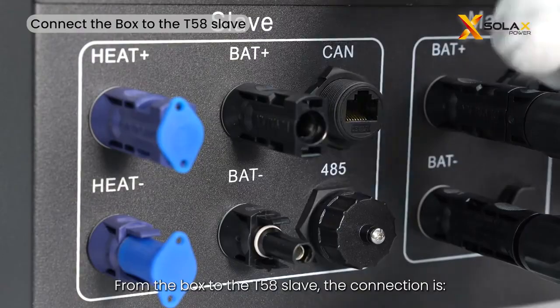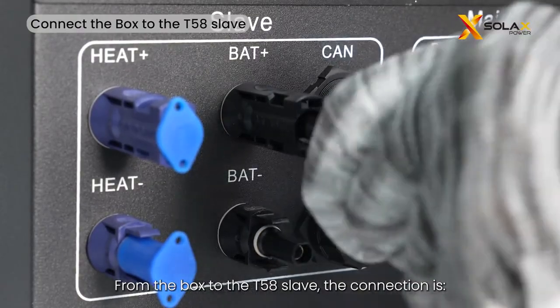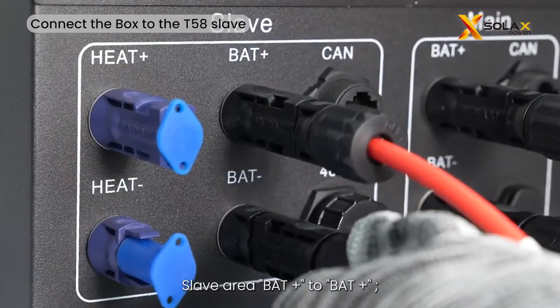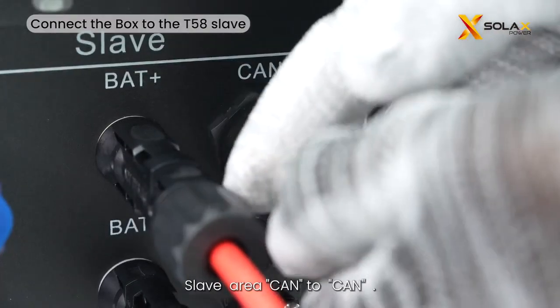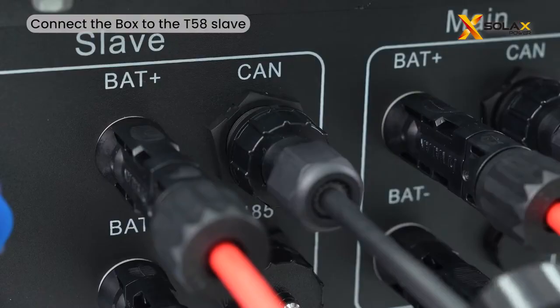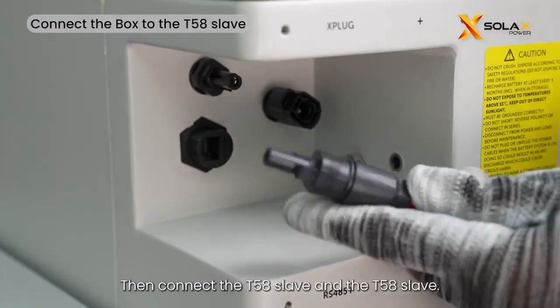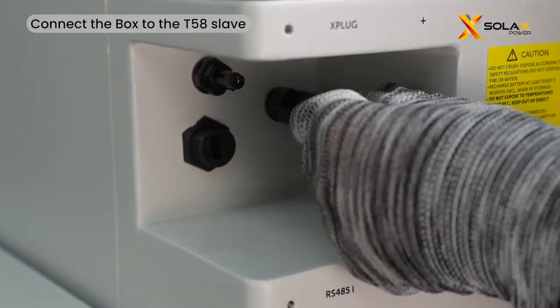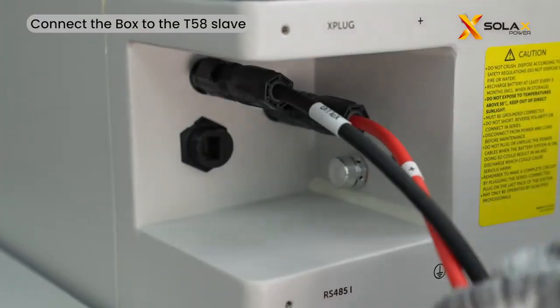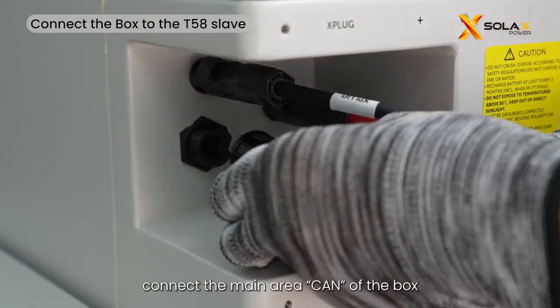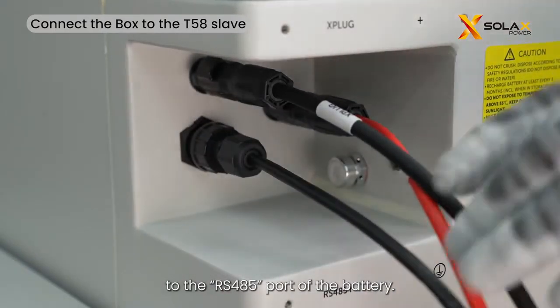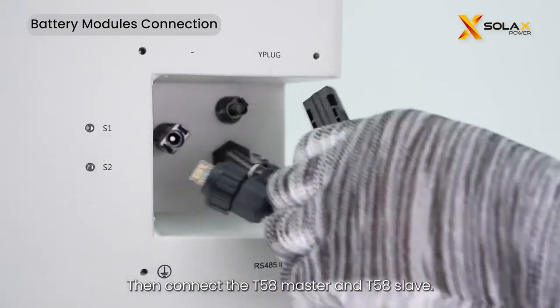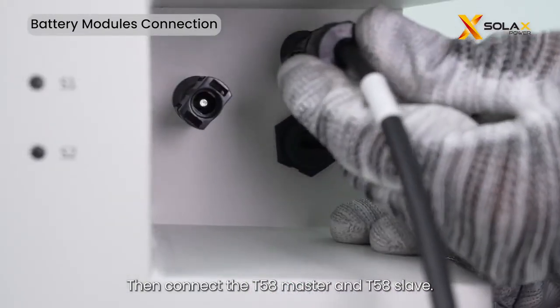From the box to the T58 slave, the connection is slave area BAT positive to BAT positive, slave area BAT negative to BAT negative, slave area CAN to CAN. Then connect the T58 slave and the T58 slave. For communication, connect the main area CAN of the box to the RS485 port of the battery. Then connect the T58 master and T58 slave.